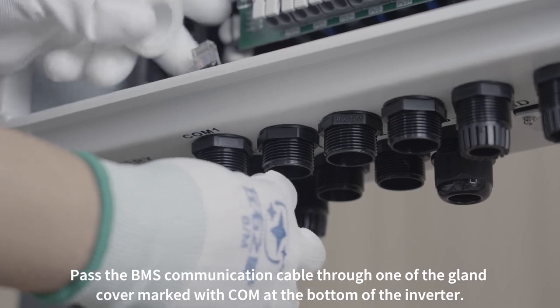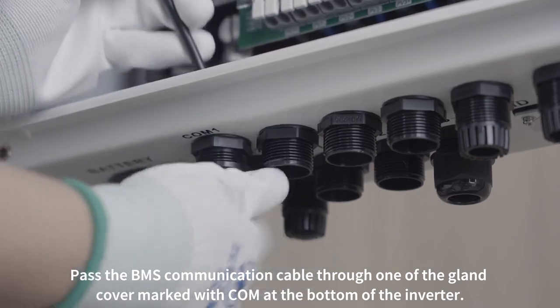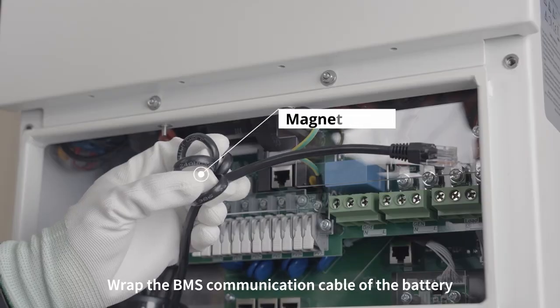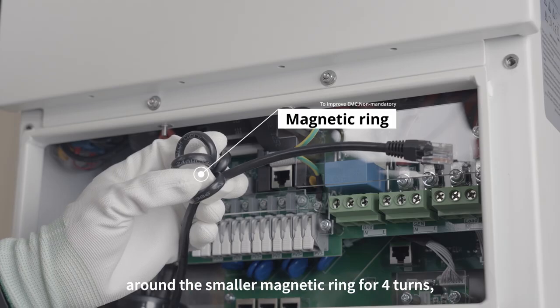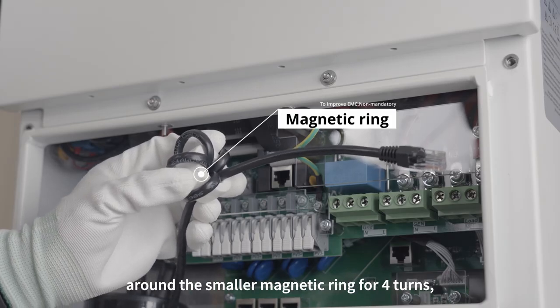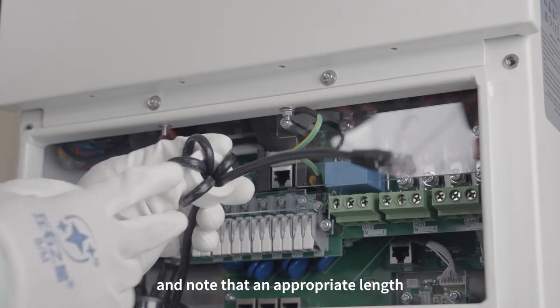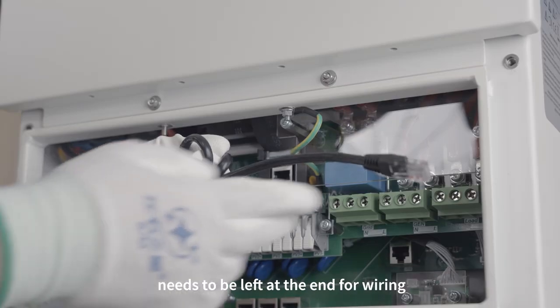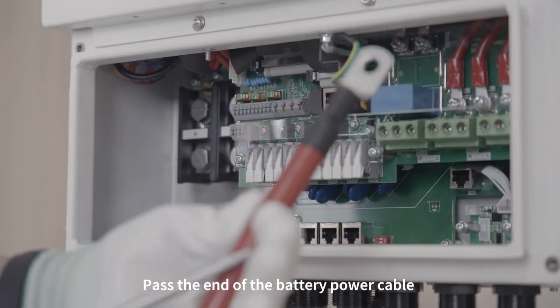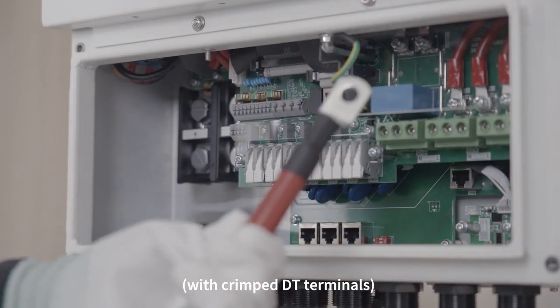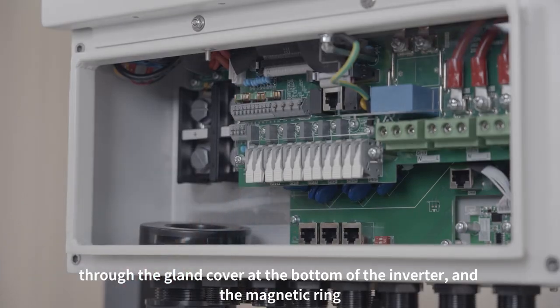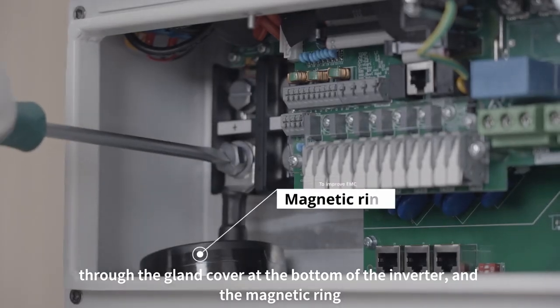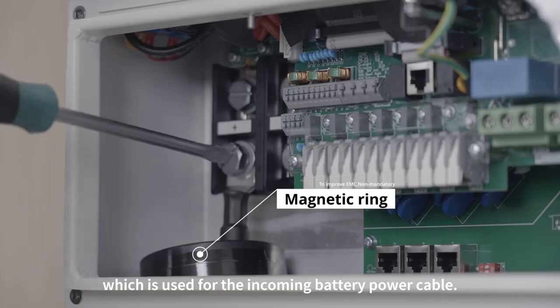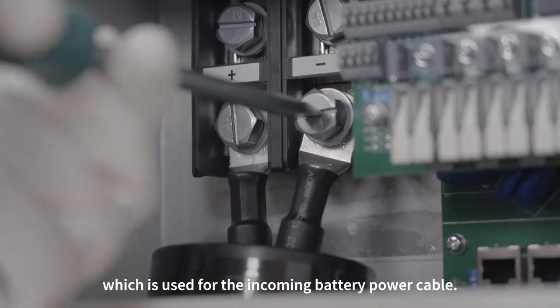Pass the BMS communication cable through one of the gland cover marked with COM at the bottom of the inverter. Wrap the BMS communication cable of the battery around a smaller magnetic ring for 4 turns, and note that an appropriate length needs to be left at the end for wiring. Pass the end of the battery power cable, with crimped DT terminals, through the gland cover at the bottom of the inverter, and the magnetic ring, which is used for the incoming battery power cable.